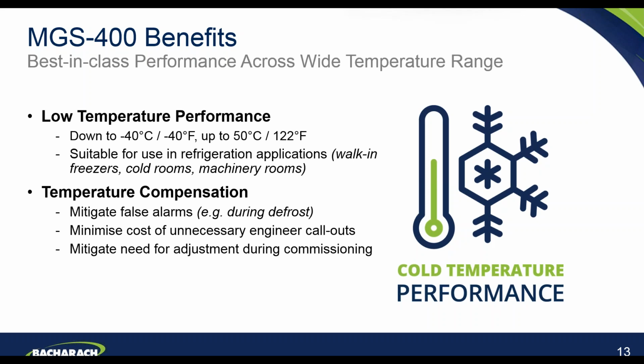The reason that's particularly important is if a sensor or a detector is not certified for the relevant temperature that it will be installed and utilized in, there are significant drawbacks potentially in terms of the performance of that sensor. Typically that will be in terms of response time, perhaps recovery time, but also in terms of the accuracy of the sensor as well. So I'm very pleased to say that the 400 series is fully certified across the range down to that low temperature point. The temperature compensation I've mentioned already.